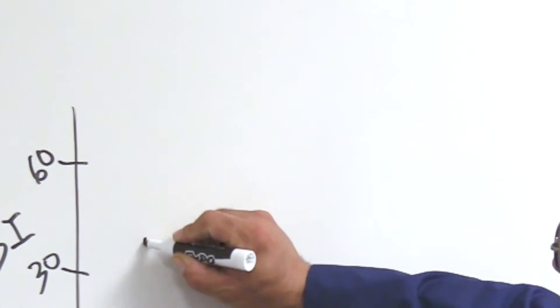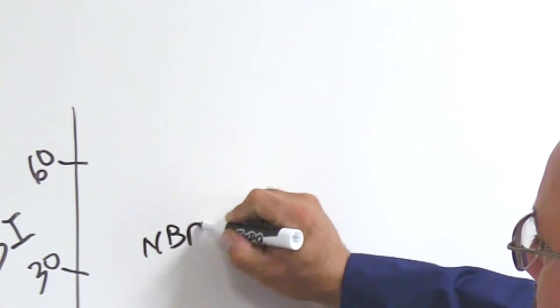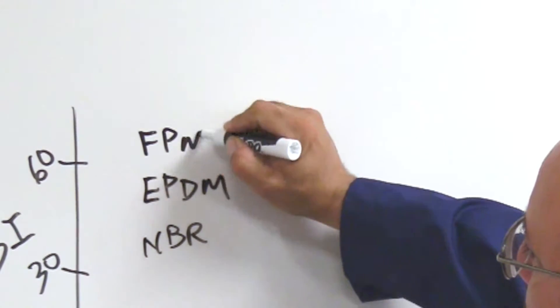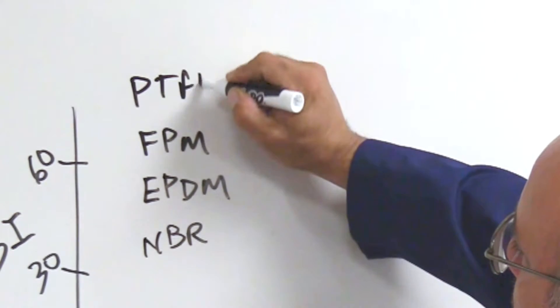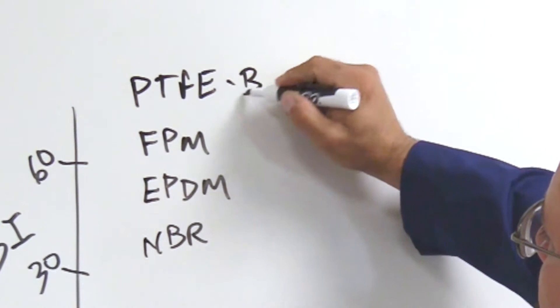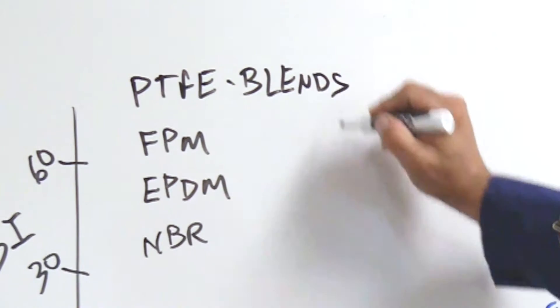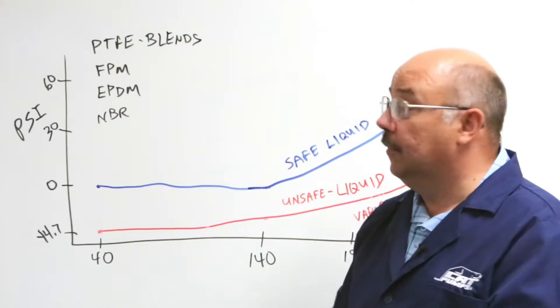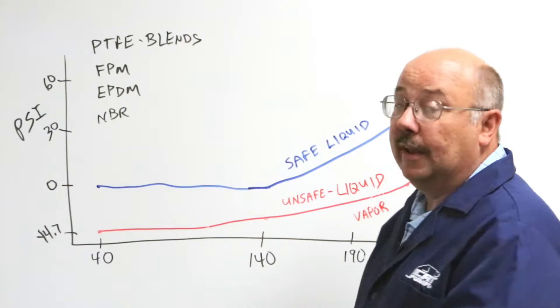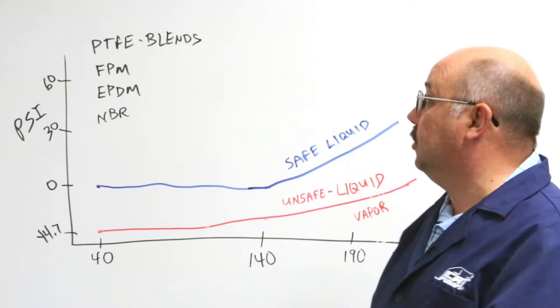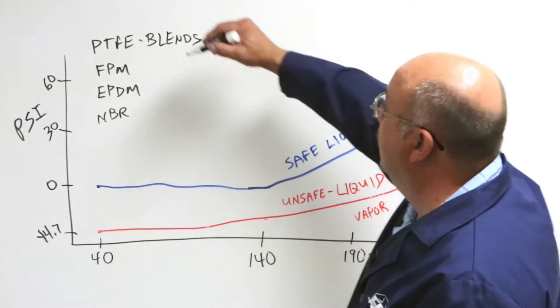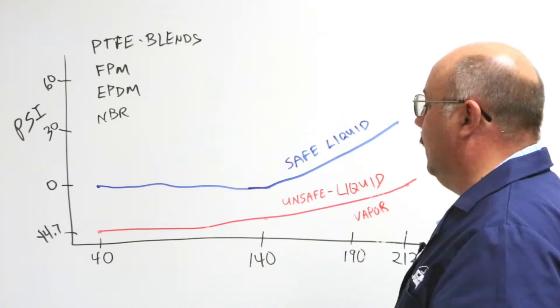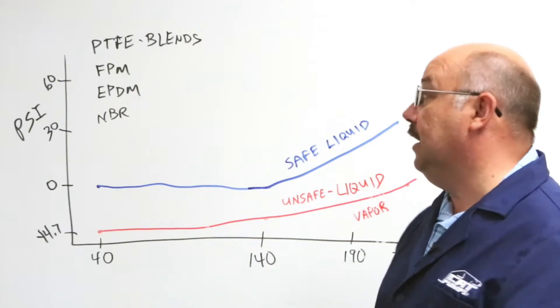We have different seal materials. We have NBR, we have EPDM, we have FPM or VITON, and we have PTFE blends. By blends I mean some of the Teflon seals that we have have carbon in them. Some have glass fibers in them. Some have graphite in them. All these things help the seal to keep its shape and to run with whatever liquid we're pumping. So we have all these different possibilities. And then we want to look at what are the temperature capabilities of each of these seals.